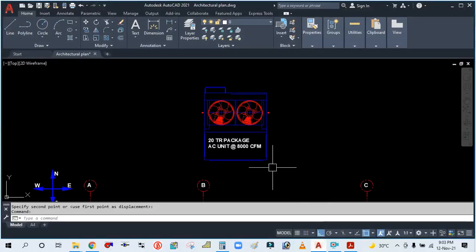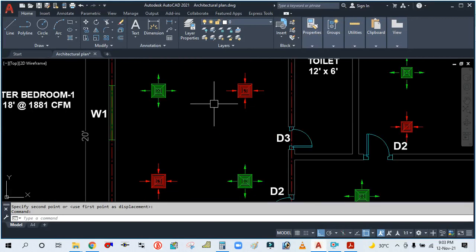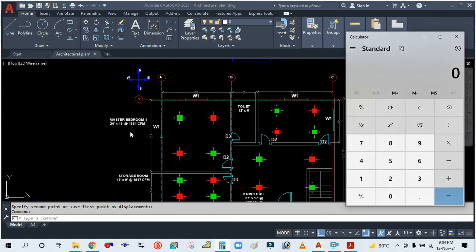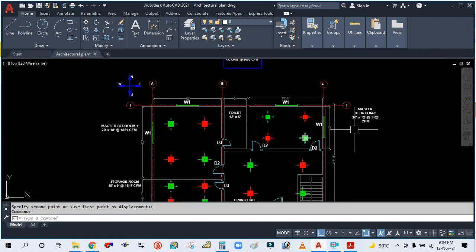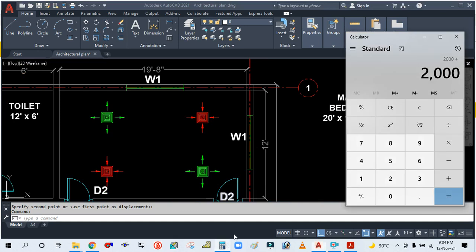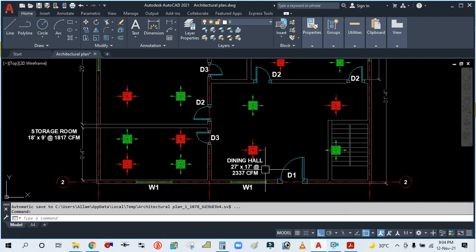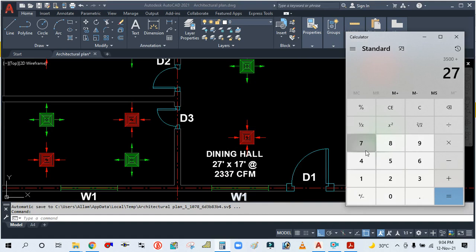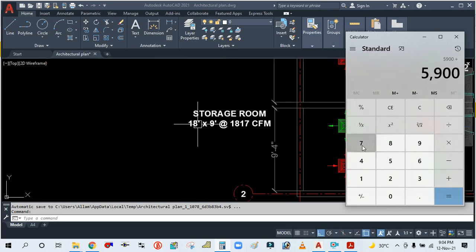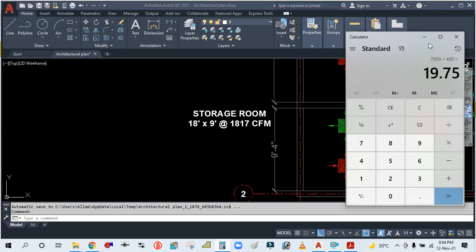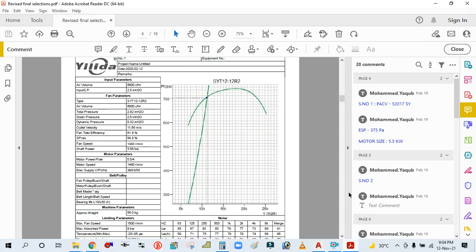The total tonnage for this floor is 20 tons. How are we getting 20 tons? Bedroom one is approximately 2,000 CFM, plus bedroom two is 1,500 CFM, plus dining hall is 2,400 CFM, plus storage room is approximately 2,000 CFM. Total I'm getting 7,900 CFM. One ton equals 400 CFM, so dividing by 400, we're getting 19.75 tons. So we'll select the machine for 20 tons.